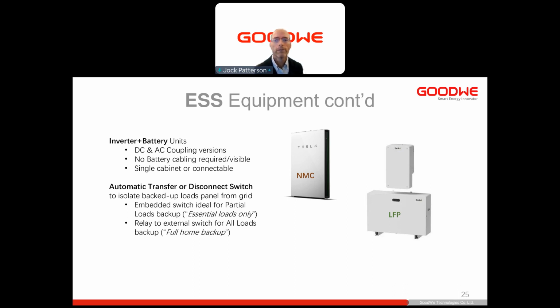In the case of switching over when the grid goes down, you have to make sure you have some sort of automatic transfer switch. And if your inverter doesn't have that built in for essential loads, then you have to get an external one. If you're doing full backup, you're going to have to get an external one. And we'll look at diagrams showing that. The beauty of these high voltage systems, although the Tesla technically is a 50 volt, is that they're in a cabinet where none of the wiring is exposed. It's very clean. It can't be exposed, and it's nice that it isn't. Very clean install.